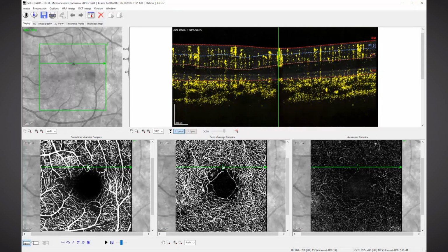And bearing in mind that the flow is inconsistent. Sometimes it's fast, sometimes it's slow, and it varies throughout the day. So sampling becomes very important. So we use our ART function, the ART of OCT, or automatic real-time mean, averaging if you like, in order to make sufficient samples of that flow through the capillary so that we have a reliable reading at the end. And just to show you that we're measuring physiology of the body, it's not OCT as we know it, and it's not FA either, it's physiology. Let me show you an example how that looks.